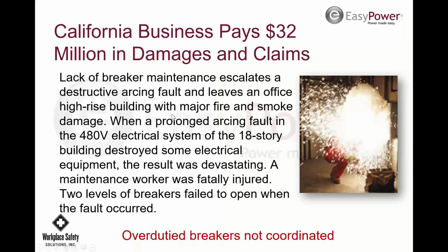But sometimes that happens. Here's a few case studies. So lack of breaker maintenance escalates a destructive arc fault, and this was an overdutied breaker that would have been picked up in an arc flash study by doing the short circuit study. So it leaves an office high-rise building in a major fire. So this is a high-rise building that had a vertical bus duct, had a main switch on the bottom, and then every floor had panels. And it failed, and it just blew this thing right up, and it ended up, one maintenance worker was fatally injured. So it's $32 million. You can do a lot of maintenance for that kind of money.